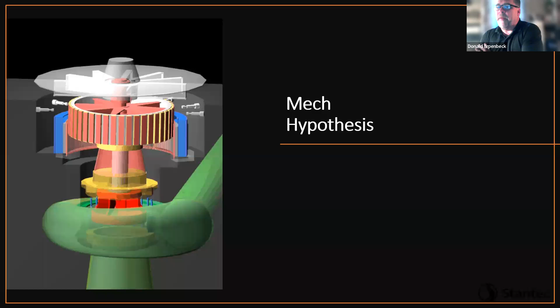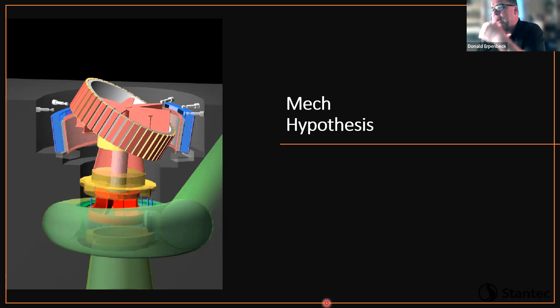So we had done a model, and this is kind of that mechanical one, which shows it lifting straight up and sort of coming off. And then the electrical one, you'll see that the generator has a wobble at the top. And in the electrical one, which I more believe, there's many more things that could cause this thing to trip and lose the electromagnetic bearing. And if those bearing bolts were loose, you get a prying action over the 10 meters of height between that rotor and the stator, and can actually pop that off and give it a large shear force between the rotor and stator. And as we showed, those arms were all torn off.